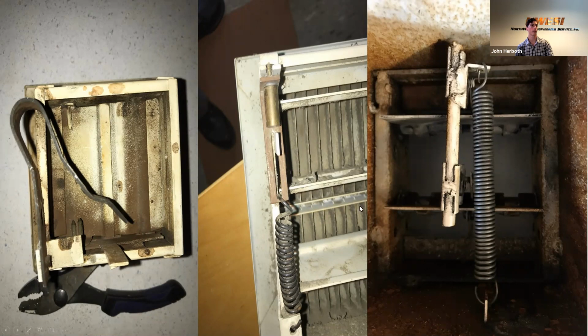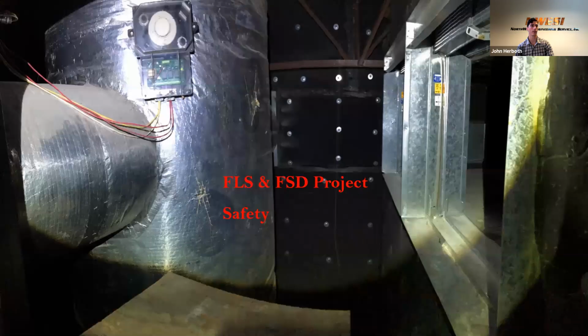Let's keep going, these were fun. You're allowed to reuse fusible links by code, as long as you can inspect them and make sure they haven't been damaged in any way. If they're coated with anything, you have to replace them. If you can't inspect it, it's got to be replaced. So as long as you service everything, you can reinstall it, you just want to note that in your table.